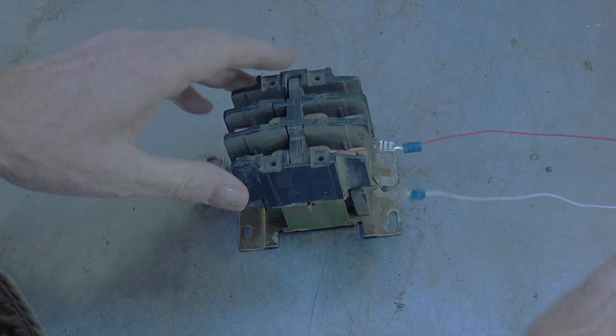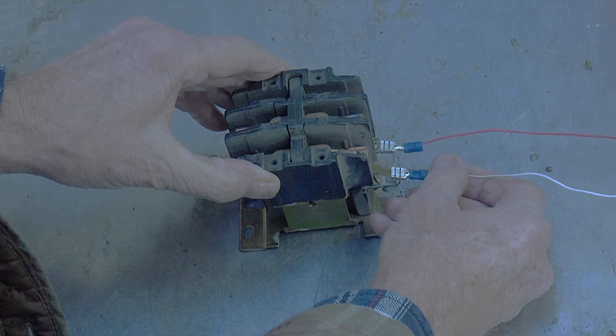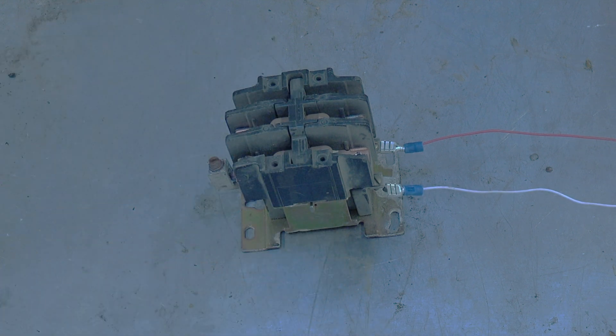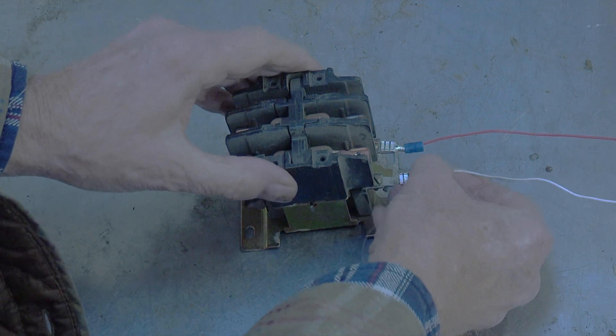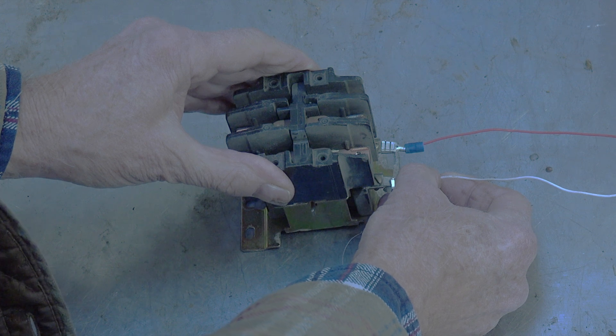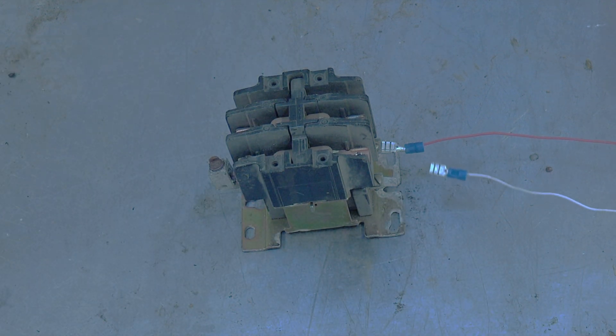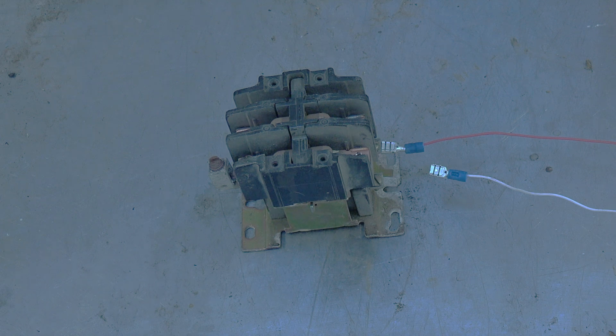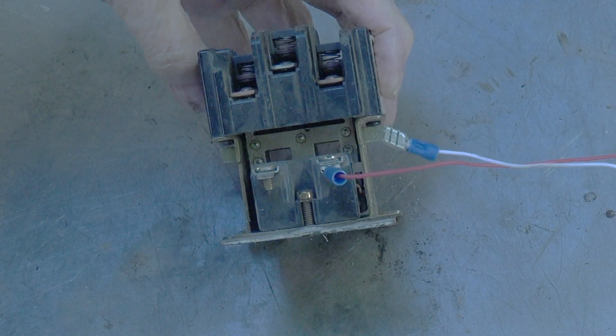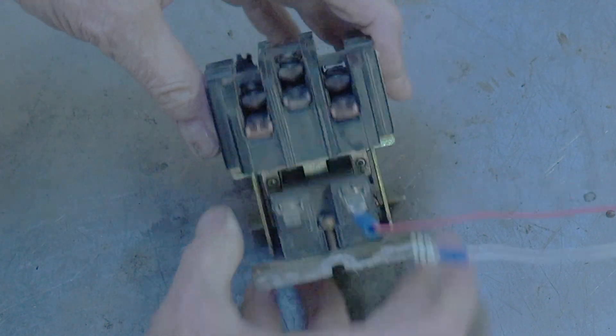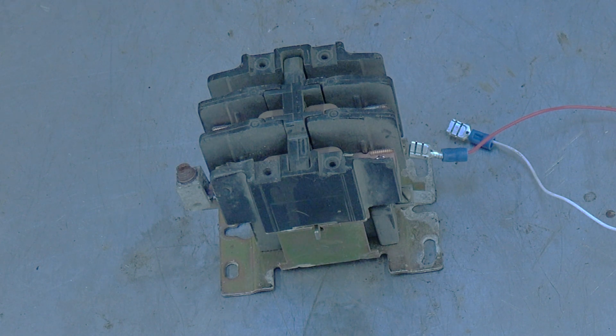This setup here is especially important with disconnect. We're engaged now where the circuit is made, and then when I let off it has to release very quickly and it has to release for a certain amount of distance. It can't just barely release. If the voltage is high, that distance has to be bigger between the two sets of contacts. If you look at this thing you can probably see those contacts there. They have to move a certain distance apart. Now this is AC.